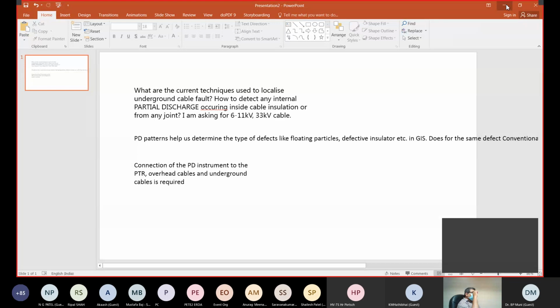The reason behind it is that different defects behave differently in different frequency ranges. You can imagine that an impulse has a much higher frequency component, and this has an influence on the field distribution inside the equipment, especially in the transformer. That is one reason the transformer is factory tested with chopped wave, because the AC frequency has a different field distribution than the chopped wave. But to my knowledge, there's not a must for both.